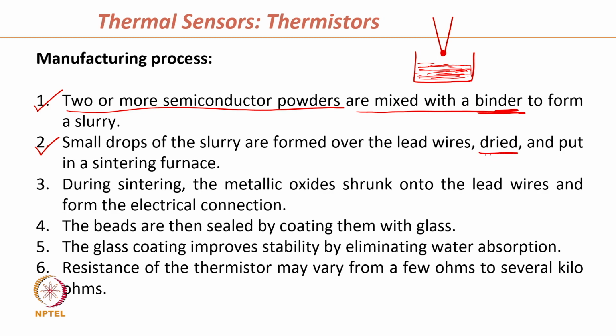We take it out, then dry it and put it into a sintering furnace. During sintering, the metallic oxide shrinks onto the lead wires and forms the electrical connection. This droplet, we call the bead. This bead is then isolated using some glass or some coating, so that it does not react with the environment. These are sealed by coating them with glass, and this glass coating improves the stability by eliminating water absorption. This should not be exposed to the humidity or water in the air.